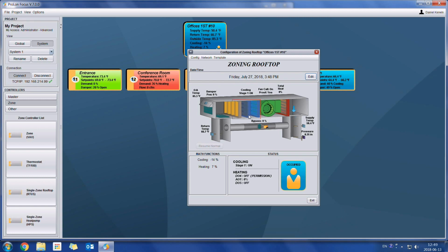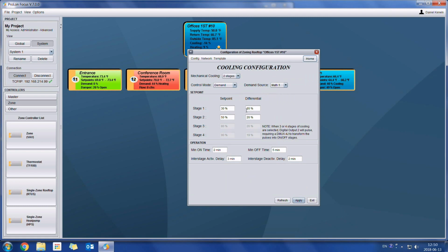So we can see the cooling stages, we can see the fan, the heating stages, and we can see the temperature in the supply, the return, and the outside air as well. Additionally, we can also look at the bypass for static pressure control and the economizer. If we wanted to configure any of these elements, we do just like we did before. If I want to take a look at the cooling stages, I can just double click on it, and it'll bring us to the configuration menu.